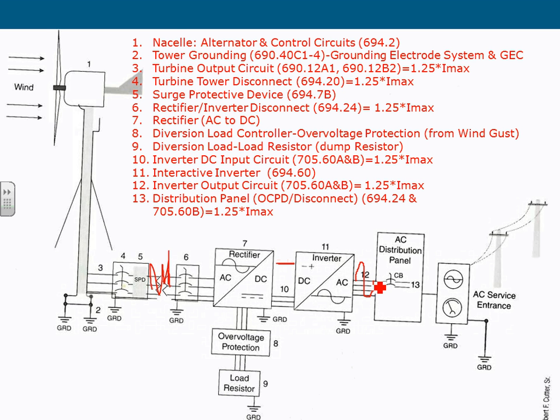If your inverter is capable of it, and there are some of them, you isolate your system here and divert this load into another panel and utilize it internally. That will meet the anti-islanding requirement, as long as you isolate yourself from the grid. I've seen an inverter that just diverts you to another set of contacts, taking you to a separate panel that feeds a separate load in your building. With a manual or auto transfer switch, because these loads cannot be connected to the two sources at the same time.